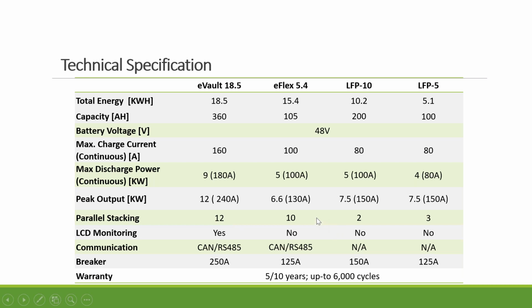The eFlex can stack up to, actually, I think here's a typing error, it should be 15. And the 10 and the 5 are stacked two or three of them. I'm going to explain why in the next slide. The eVault and eFlex can have closed loop communication with inverters. For the 10 and 5, you will be setting up the parameters in the charge controller and inverter, and that way the inverter and charge controller can manage charging and discharging of the battery.